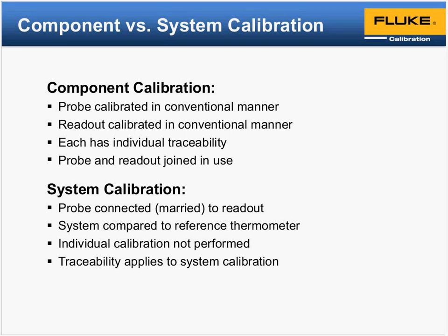The reason you move to an external reference thermometer is simply going back to the grade of sensor in the actual component, where we're not absolutely accurate. I'm not going to use an SPRT grade sensor. There's also cycling up and cooling down, where you're going to see some history that's hard to compensate for. So the spec of the heat source tends to be wider than a reference. It's basically the internal component, so we're not using a measurement circuit versus a thermometer, which has its own built-in reference that we use to help interpolate. So again, it just comes down to a difference.